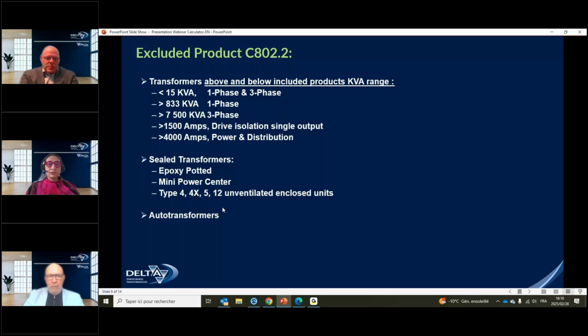Drive isolation above 1,500 amps, sorry, is excluded. All non-ventilated transformers, so NEMA 4, NEMA 4X, mini power centers, epoxy potted transformers, those are excluded. All autotransformers are excluded. So for all of these products, we don't have to meet any minimal efficiency. So there can be big variances from manufacturer to manufacturer in regards to the losses and the efficiency of those products.